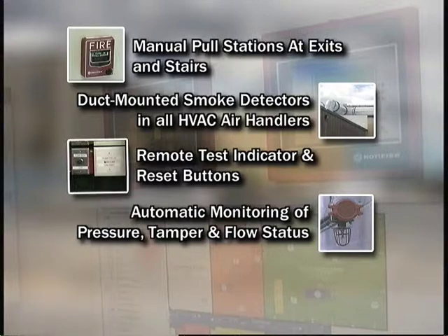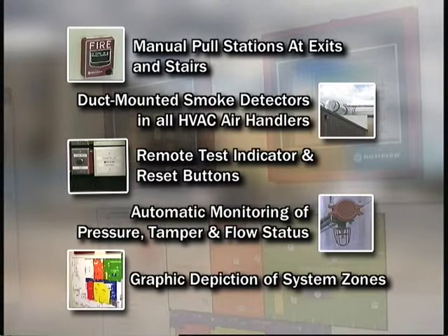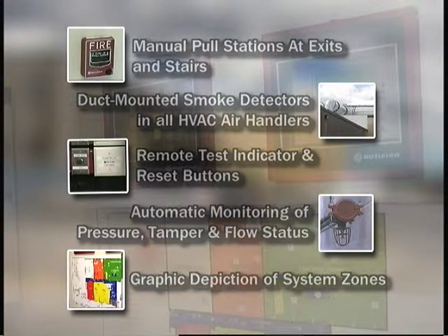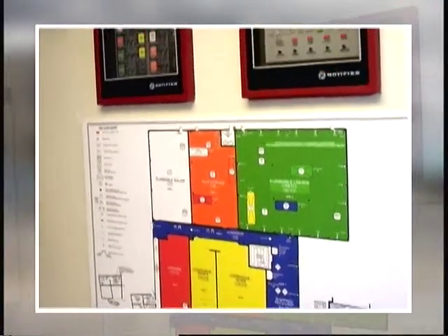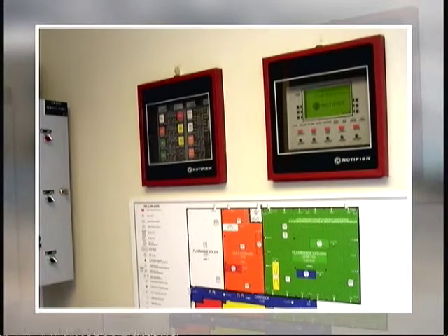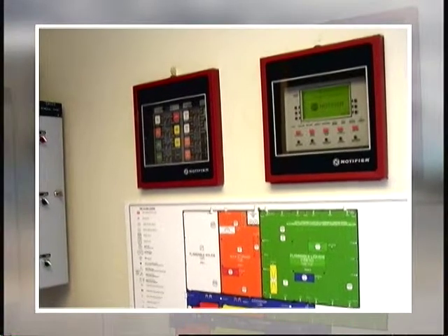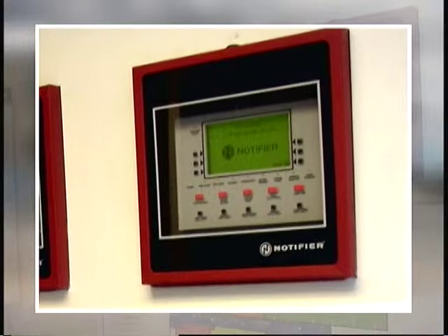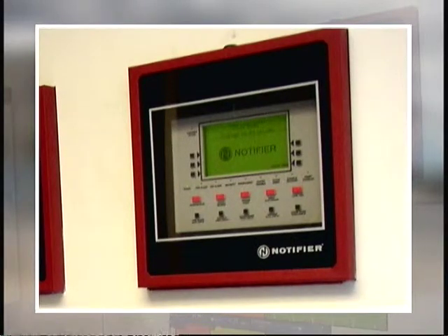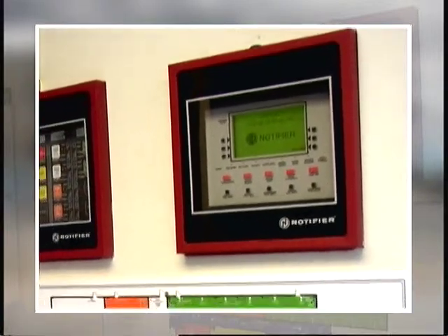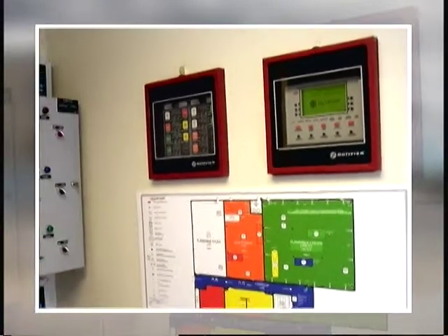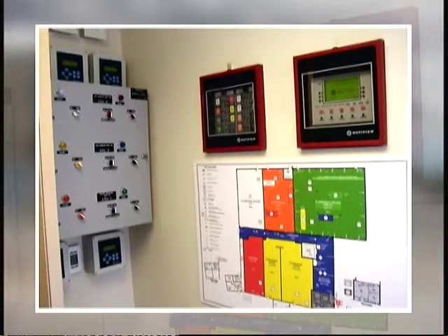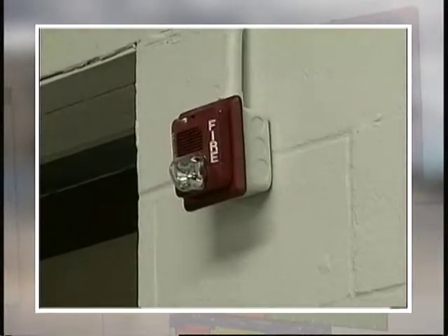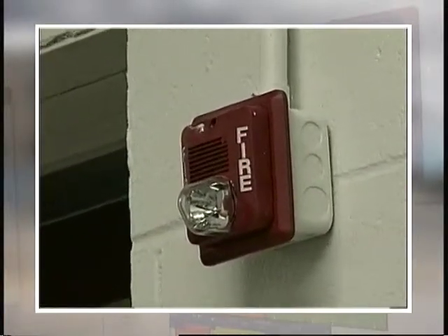The building fire alarm zoning is geographic in nature and essentially follows the building areas defined by this drawing, shown graphically on a Lexan fire alarm directory located at the main entry. The system includes a remote annunciator with test, system silence, and system reset switches behind a locked cover. The annunciator is located in the main entry lobby with the graphic directory located adjacent to it. The building is equipped with strobe and horn appliances.